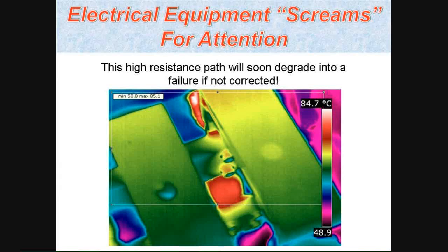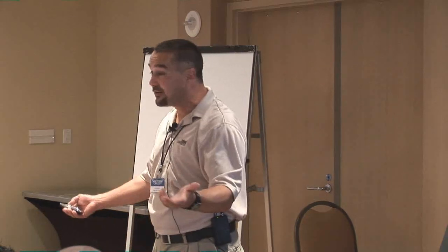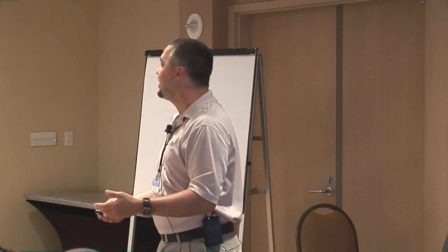But he would not have taken the steps to look at this image in this fashion without the Ultraprobe. And an outage was scheduled. They're going to clean this up, but it's going to get dirty again. They've got to do some other things engineering-wise in this room to prevent that from happening. But again, a failure was avoided here.